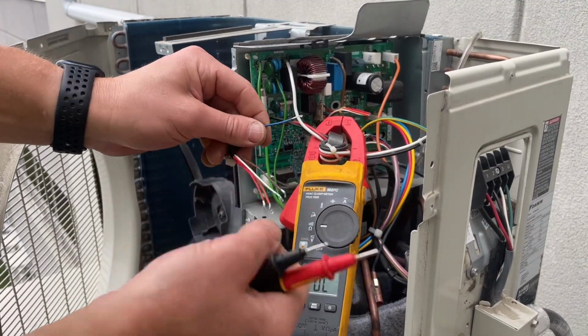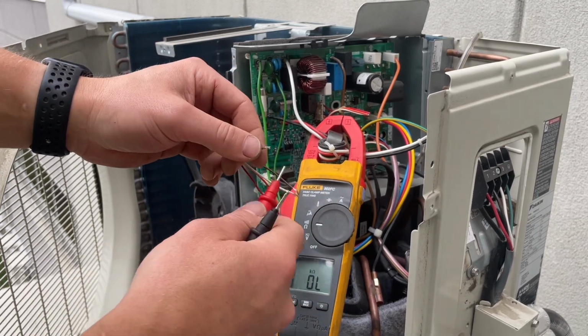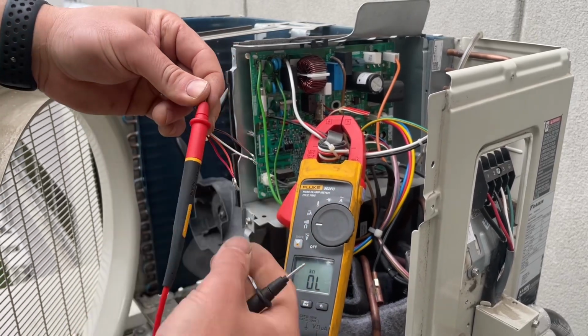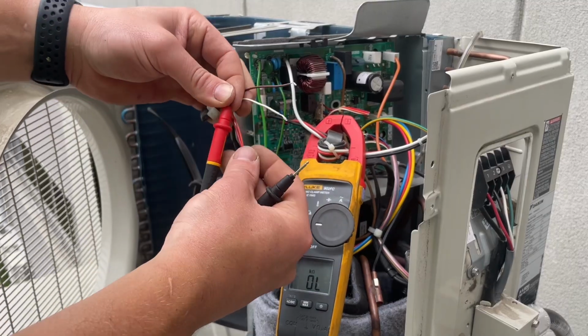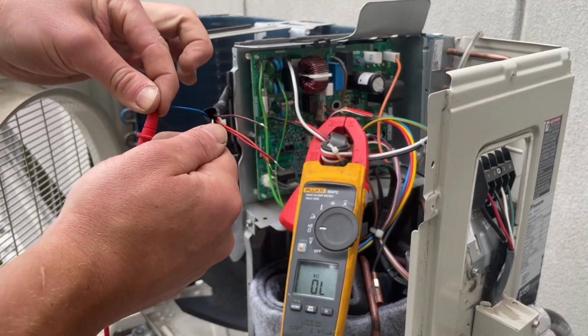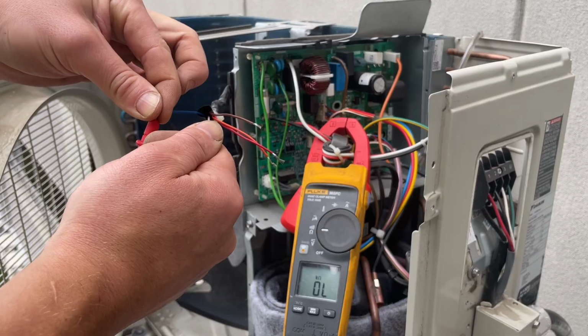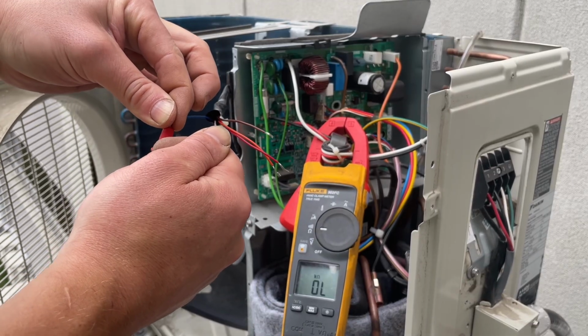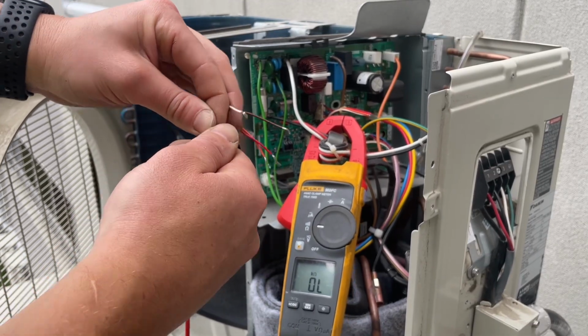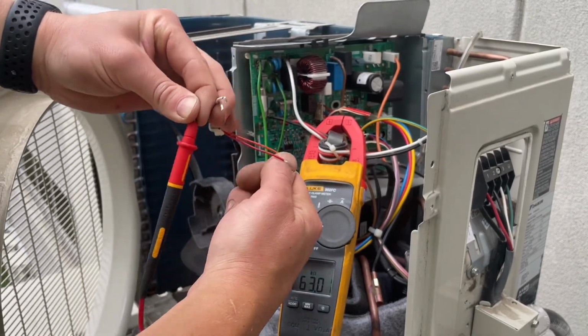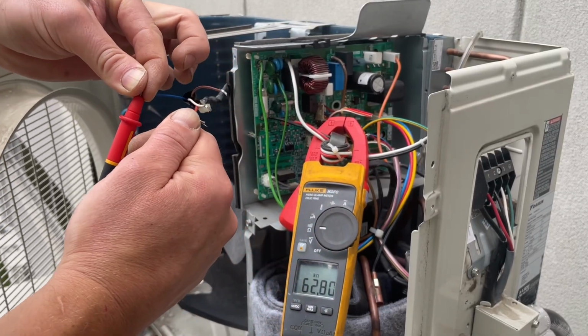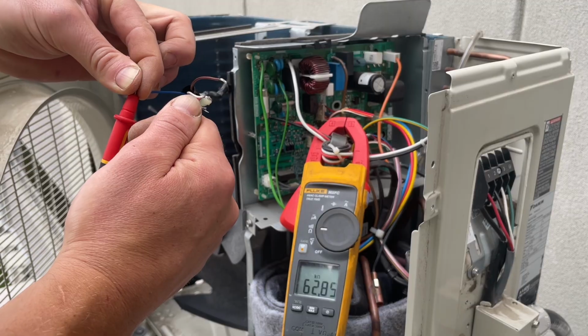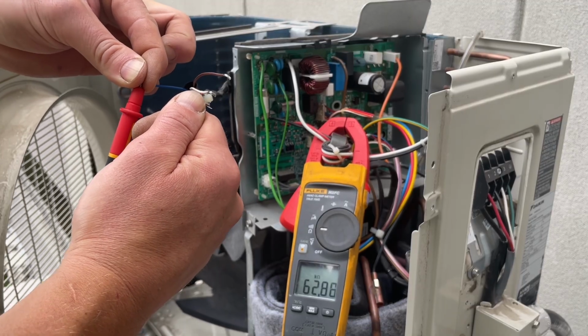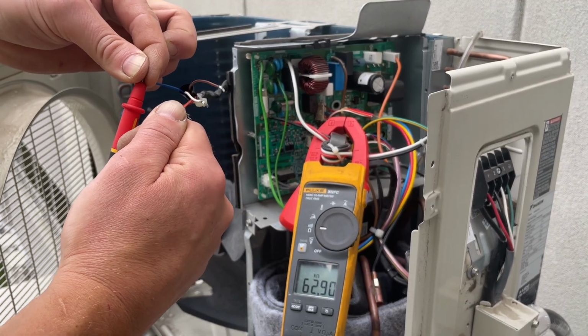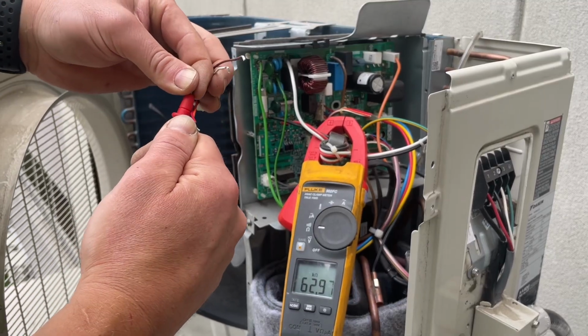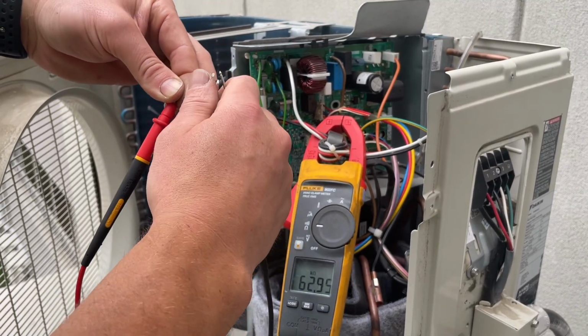So keep in mind, we have 5 wires for our condenser fan motor. Remember this, blue on this particular Daikin system is always our common. So we're going to start with blue to white, and the reading we should be getting is 1 mega ohm or more. We have open windings, out of limits. So that's not a good sign. Blue to orange. Let's get a good read here. We have 62.8 kilo ohms. That's not good. We're looking for 100 kilo ohms or more on our blue to orange terminal. Next, we can check our blue to brown.